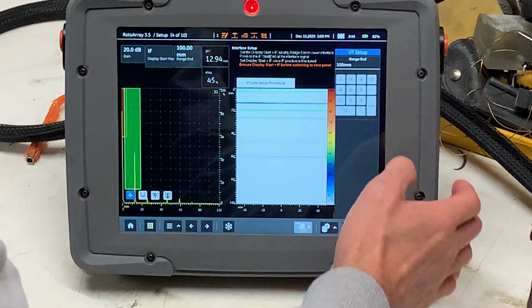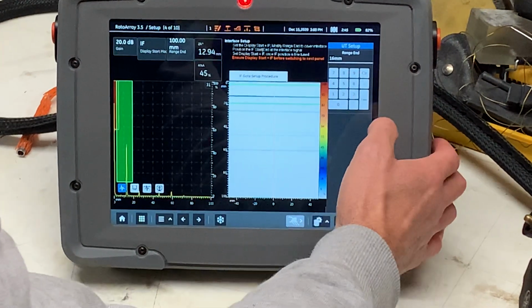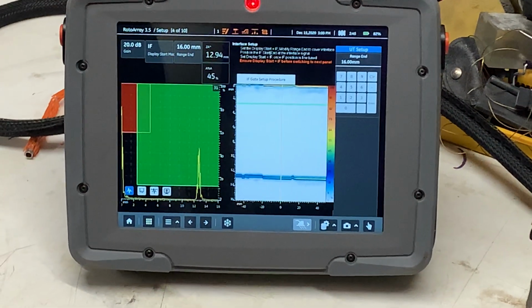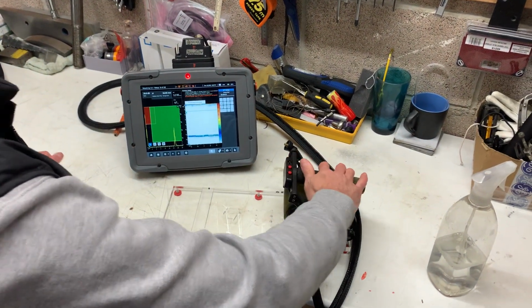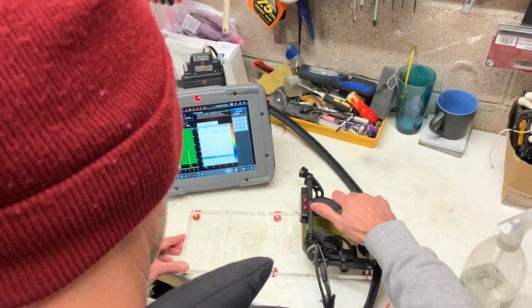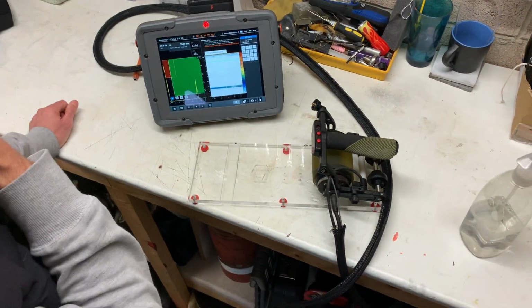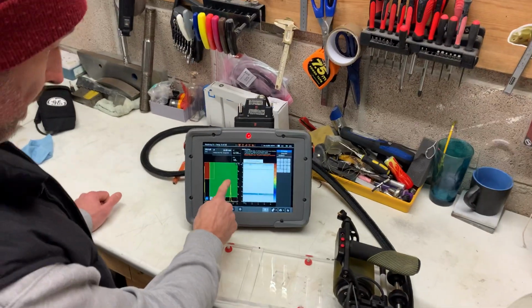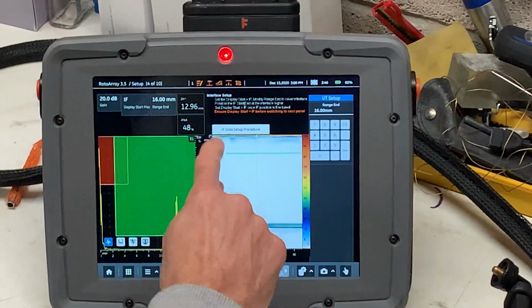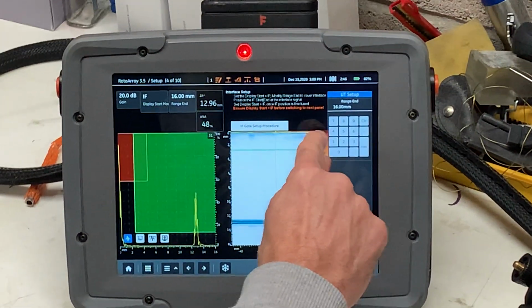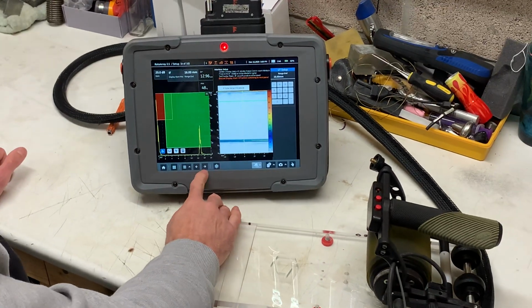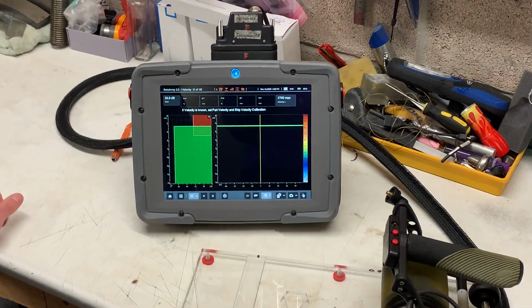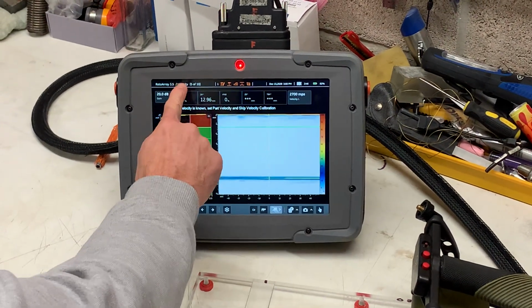And then we're going to put our range to something sensible for this inspection, 16 millimeters. Okay, that's pretty good there. Just move it around. Yep. So now we can see the signal from the back wall here, and this is just the top surface signal here. So we're pretty good. With the next page, we're going to do a velocity calibration.